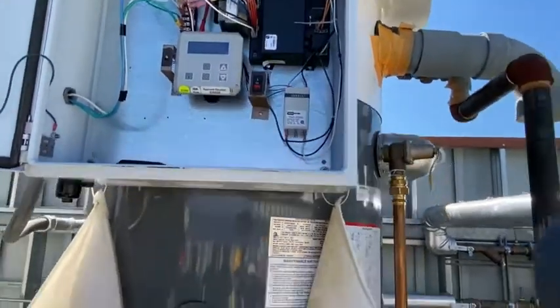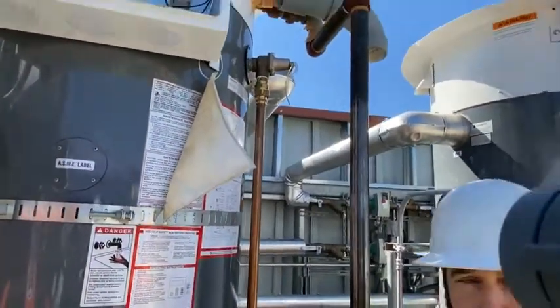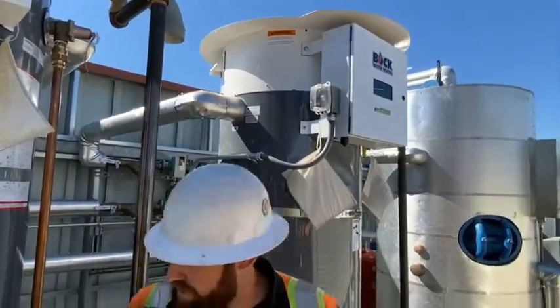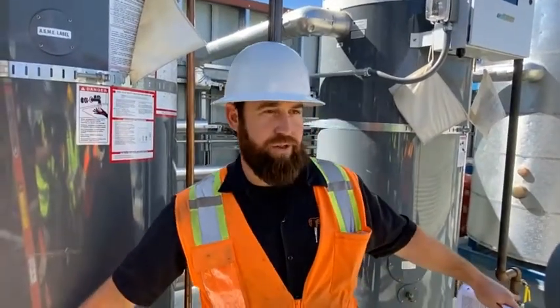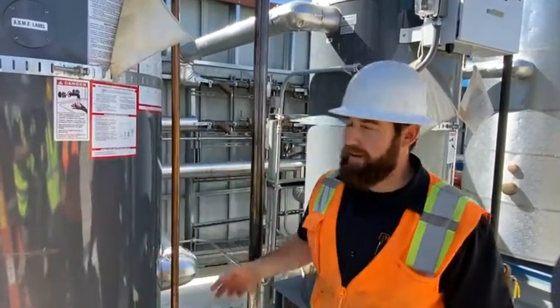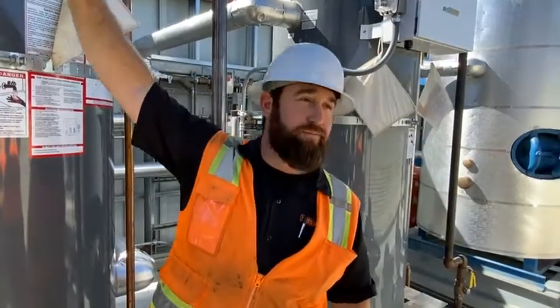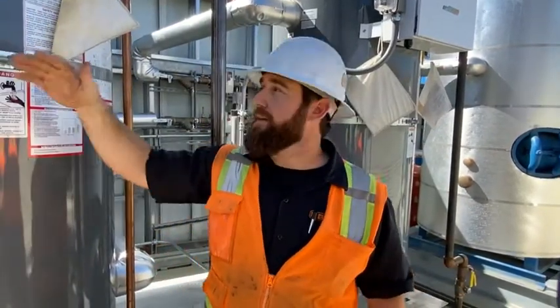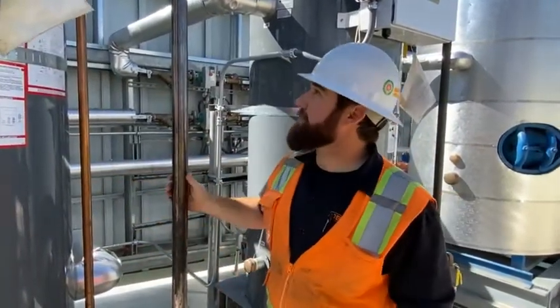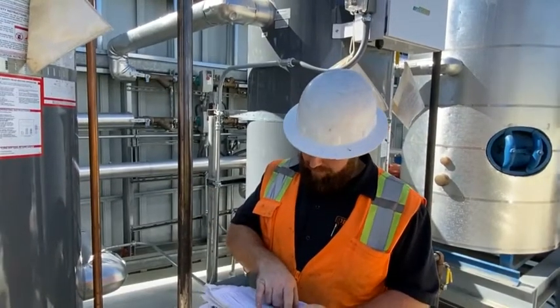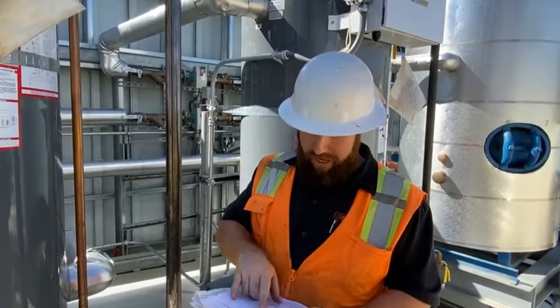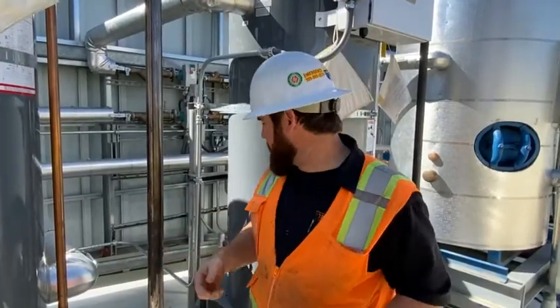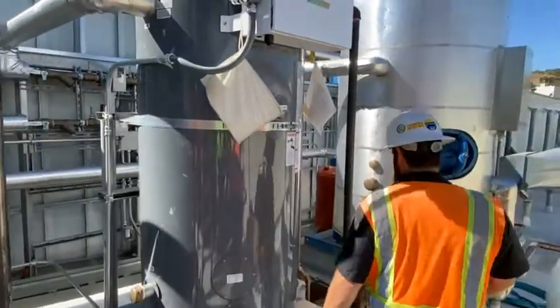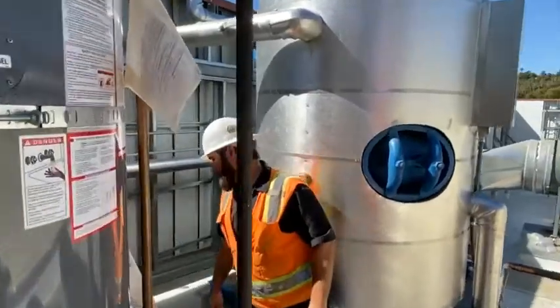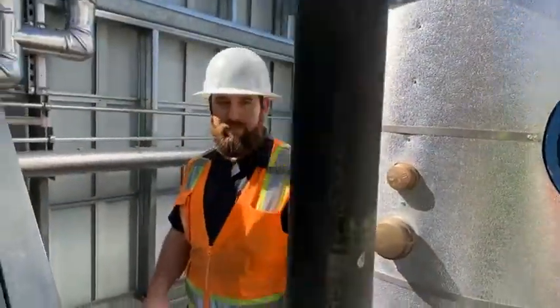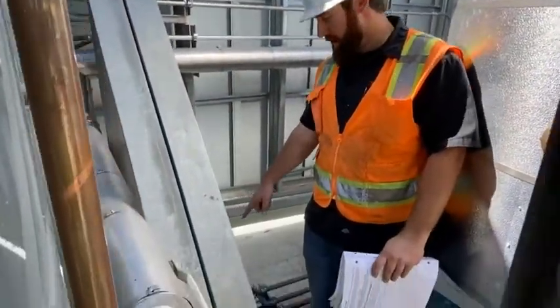Every 6 months, it says to flush the tank. So you'll have to isolate and then use a drain here, get a hose, drain it down, then refill it back up. Make sure you shut down power before you isolate and drain. Check the condensing trap every 6 months, which are over here, down here on the ground.